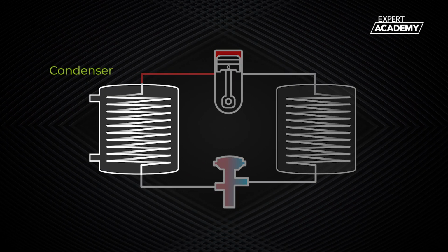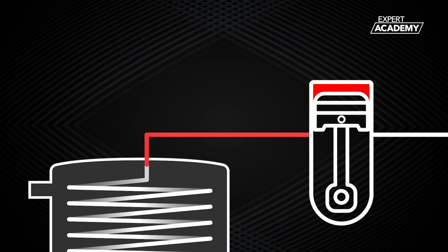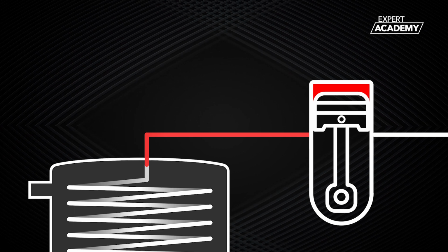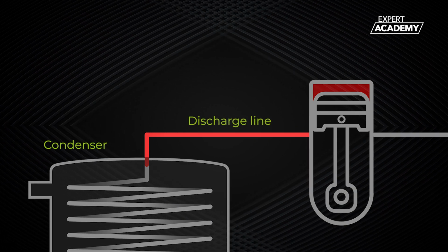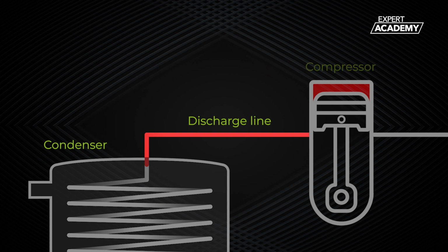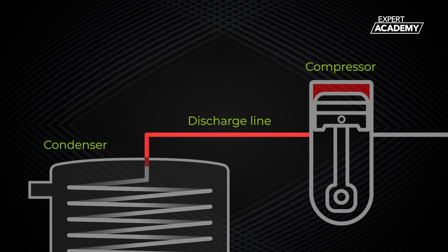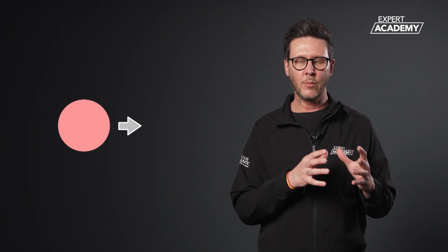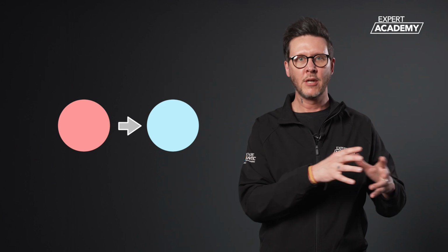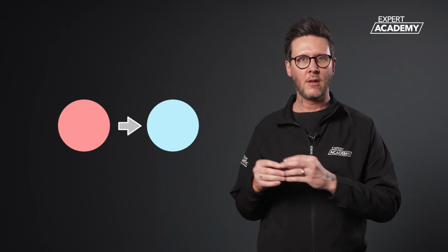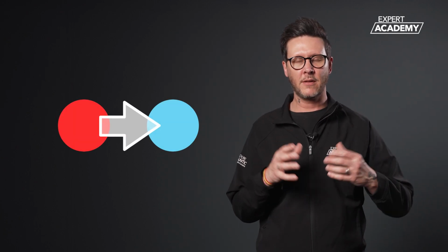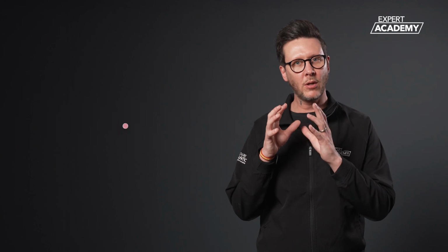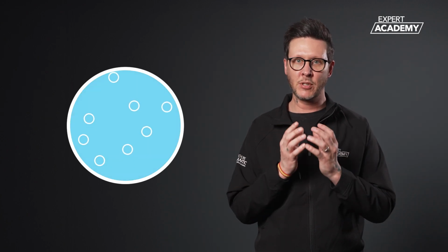The next stage is the condenser. The high pressure, high temperature vapour enters the condenser via the discharge line. The discharge line connects the compressor to the condenser. Remembering that heat moves from areas of higher temperature to areas of lower temperature, the greater the difference, the bigger the transfer, and when we cool a vapour down, it condenses, changing state from a gas to a liquid, releasing or rejecting the heat energy it has absorbed.